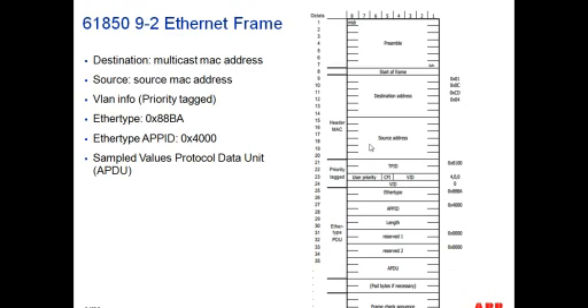Then you have a source address, which is the hardware MAC address of the device that's publishing this information. Then you have the 802.1Q protocol tag, with the priority and VLAN ID. Then we have 2 octets for the EtherType, the type of protocol being encapsulated in this Ethernet frame. In the case of 9-2, that's the 88BA EtherType. Then the EtherType APPID, which is 4000. And then we have what's referred to in Ethernet lingo as an APDU, or Application Protocol Data Unit. Essentially, the APDU is the sample values related information.